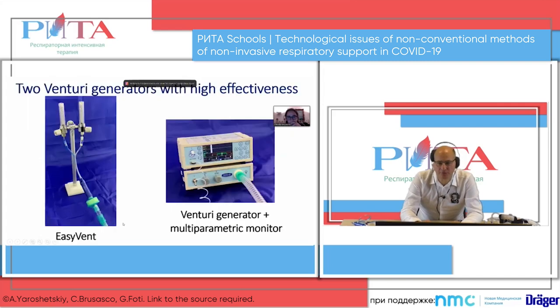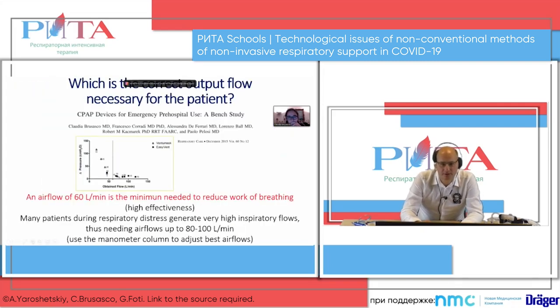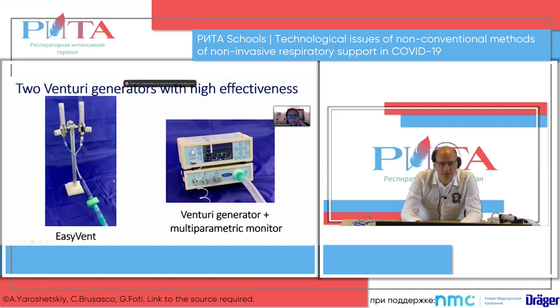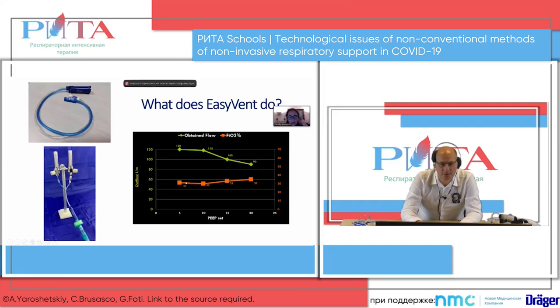Can you show us the table of the flows, resulting flows, and the FiO2 and CPAP? Yes. This is the study I did to understand the minimum airflow output needed, which is 60. You see that above 60 you have a decrease of the delta P, the work of breathing, and if you give the patient less airflow output, the less you give, the more it increases the delta P, okay? These are the two Venturi systems I use, and this is what this Venturi system does. So you see, with 5 of PEEP, 15 liters here, I get 120 of airflow output with 31... of FiO2.